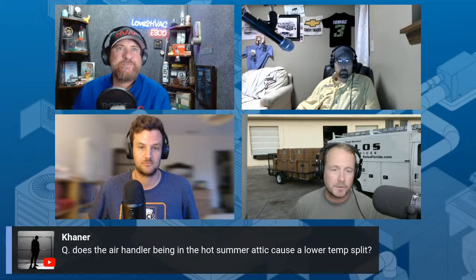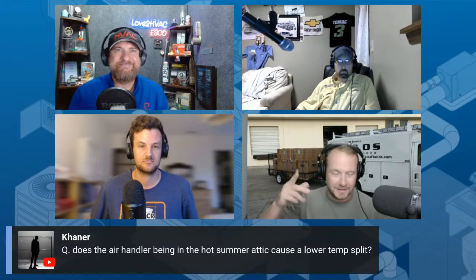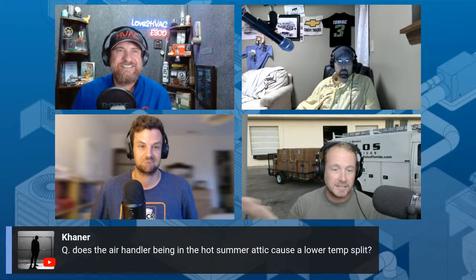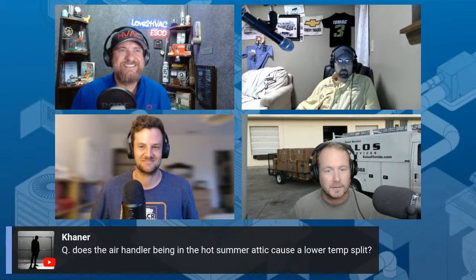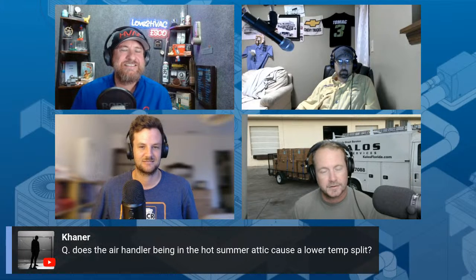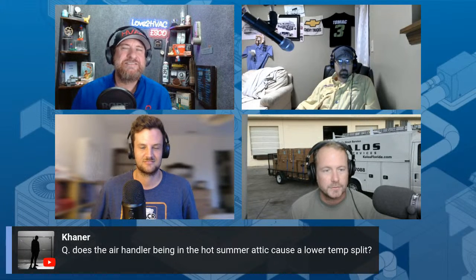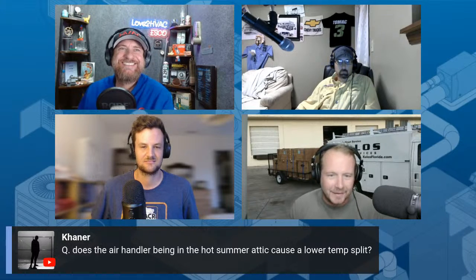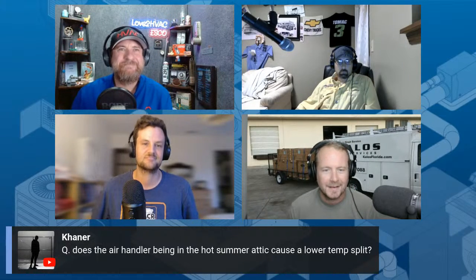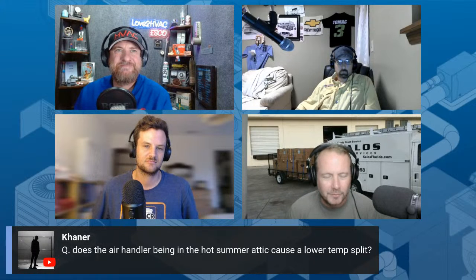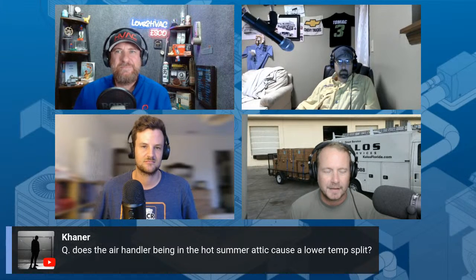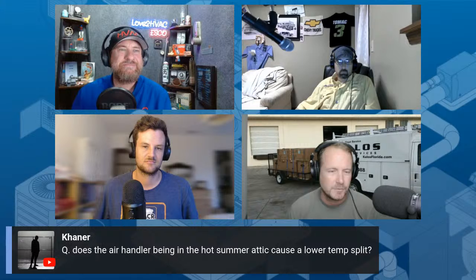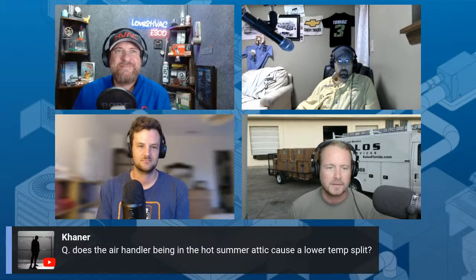That's actually something that Bryn Cooksey calls a duct efficiency test, and that's exactly what he does. He divides those two numbers and comes up with a percentage, basically saying this is the percentage of capacity you're actually delivering based on what the equipment's producing. It's a good way to assess whether there are things you should be doing. Now, you can say it's just the ductwork, but it's not just the ductwork - it can also be the attic. If your attic is 150 degrees because it's poorly ventilated or whatever the case may be, that's another factor you may not have a ton of control over, but it's certainly something to consider.